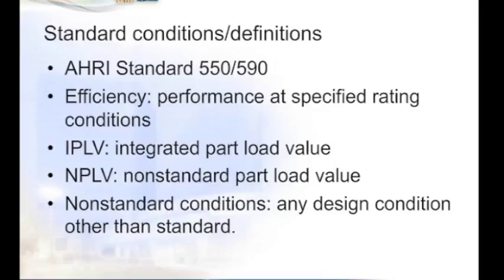And when we talk about efficiency, it's defined as the performance at specified rating conditions. The IPLV, or the integrated part load value as defined in 90.1, is a single number figure of merit based on part load EER, or energy efficiency ratio, COP, or coefficient of performance, or kW per ton, expressing the part load efficiency for air conditioning and heat pump equipment on the basis of weighted operation at various load capacities for that equipment.